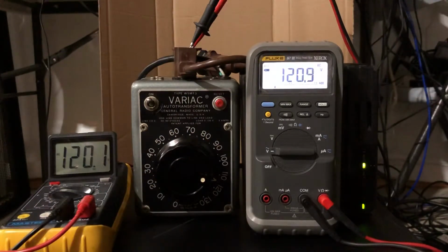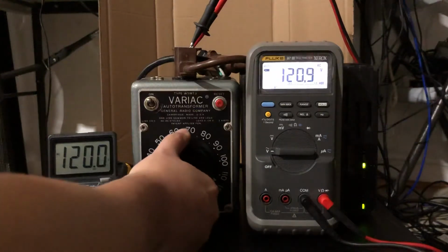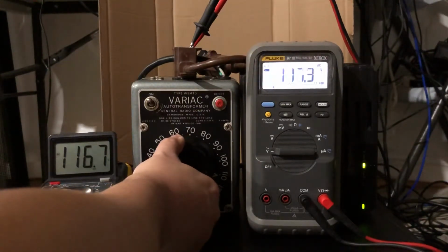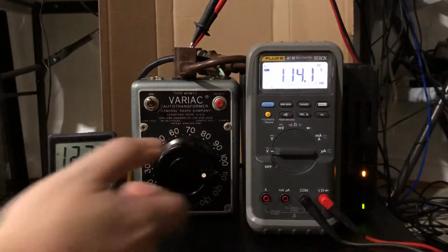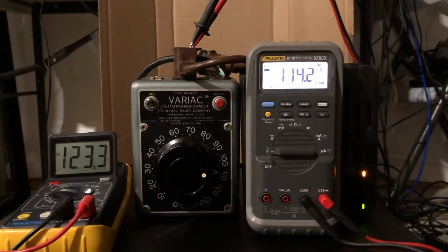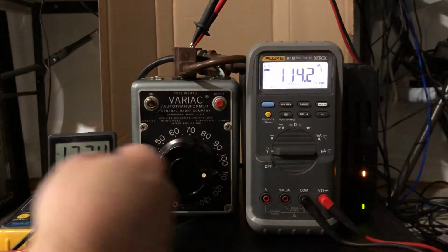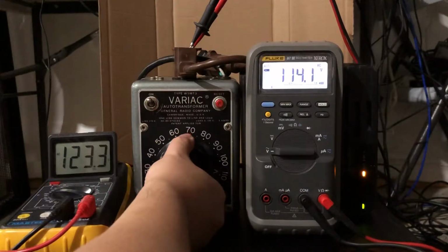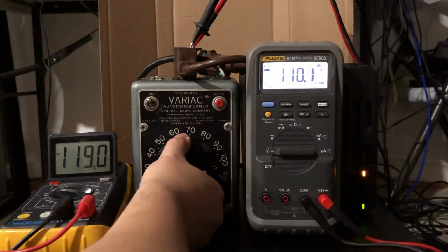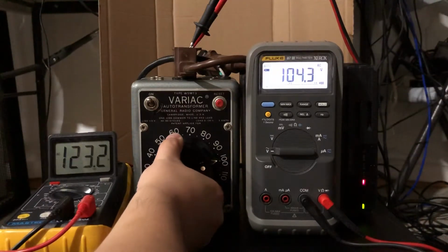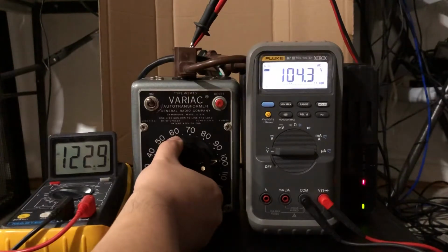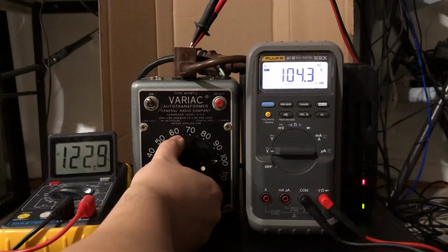Now we're going in the opposite direction. Now the system is boosting, because we're at 114 volts, and it went back up to 123. We're at 110, the output is 119. And it's bucked again, so we're at 104, the output's 122.